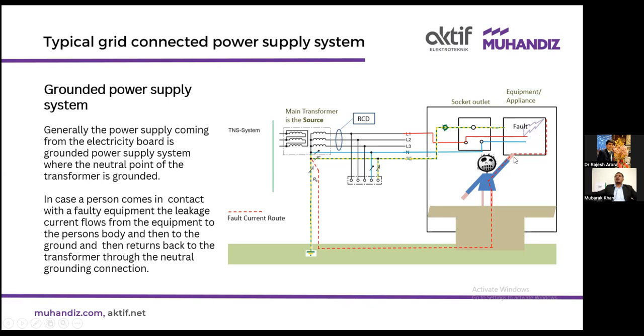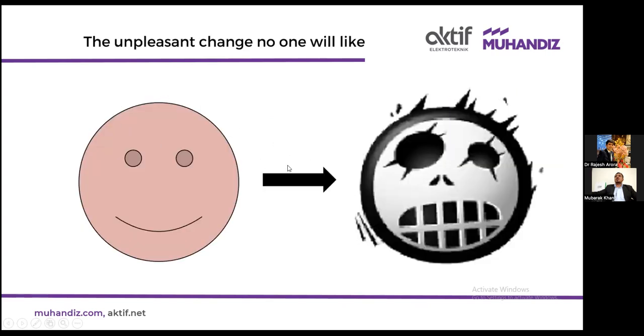In that scenario, if a person touches the body, then the current will flow through the person's body, go to the ground, and go back to the transformer. This will complete the loop. The person will get a severe shock. The RCD may or may not trip depending on the amount of current flowing through the person's body. So, from a smiling face to an electric shock affected person, it is really painful. If you have witnessed someone who has got an electric shock, you must know it is not at all funny.